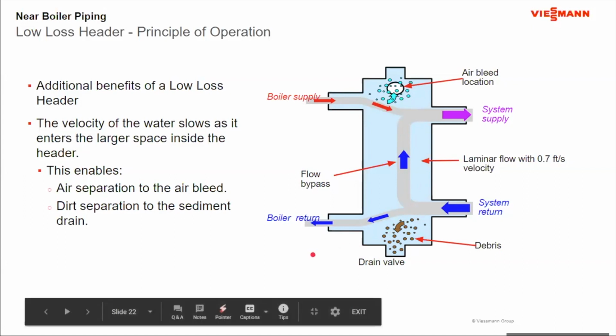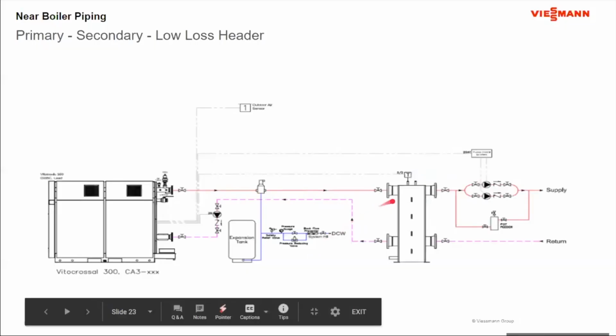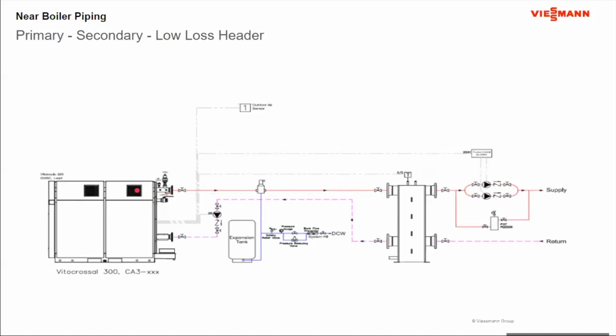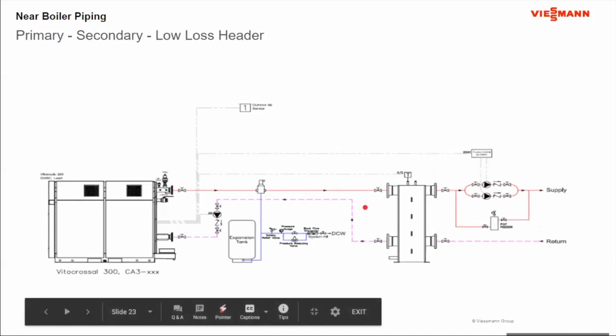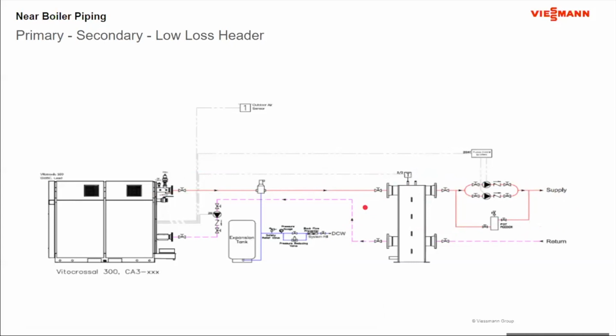So from an application standpoint, the low loss header replaces the closely spaced tees. So here's the boiler out here. Here's my low loss header. Here's my system supply out here. The boiler is hydraulically separated from the system, so I can pump that boiler at the rate that's required for the boiler. And the system over here can either run at a fixed rate or run variable based on the needs of the building. Okay.